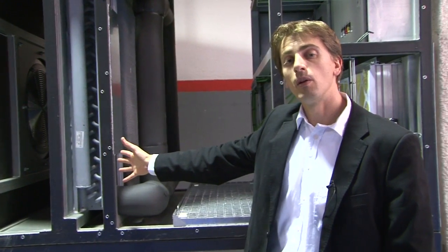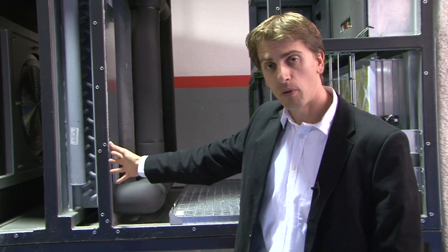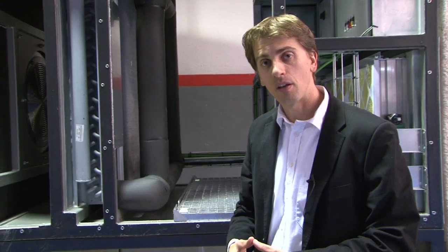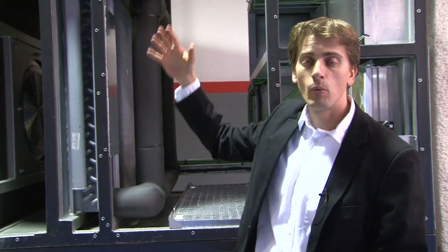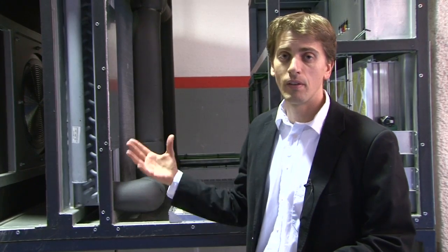This is a chilled water coil type of deployment. These units can be deployed as well with direct expansion, and in that case the top part of the unit would be used to provide condensers, compressors, and all the units necessary in order to provide the 50 kilowatts of power that the unit is capable of handling.